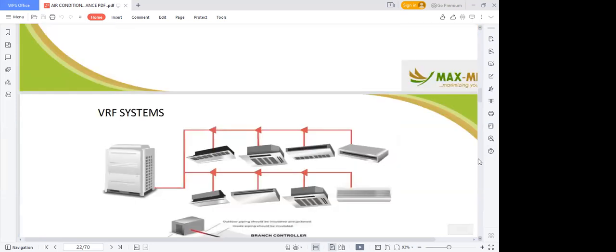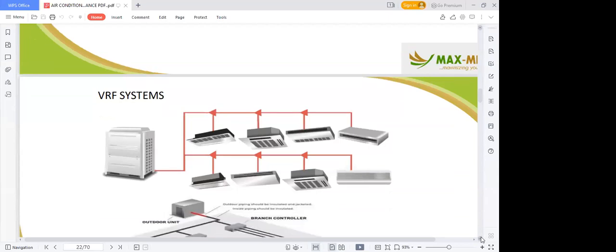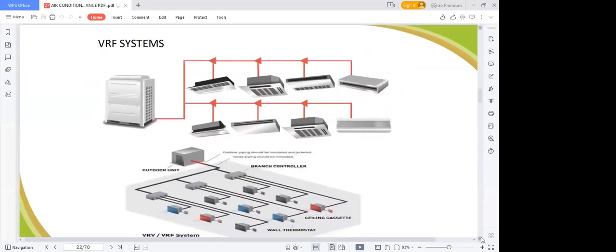So then we have what they call the VRF system. The VRF system capitalizes on the disadvantages of space. When I showed you the chiller, you saw how massive they are. They occupy a lot of space. But a VRF system has the capacity of a reduced space, yet gives maximum cooling. Most of them also work on direct inverter compressors, inverter driven. And they also have the capacity to work with various kinds of indoor units.